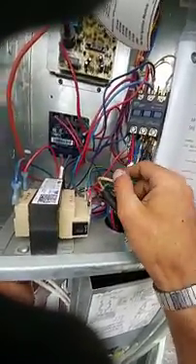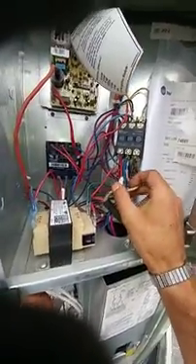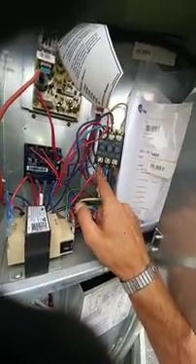For the power exhaust wiring, you've got your main power wire right here. All you have to do is take the screws off the top, pop it, run along the top of the chase, and I ran mine up the back and then down — pretty simple. Landing on the terminal strips they're color-coded: white goes to blue. You have red, black, white, and ground — ground goes to ground, red goes to red on your line side. These all go to your line side, and the control for that is handled through the board.